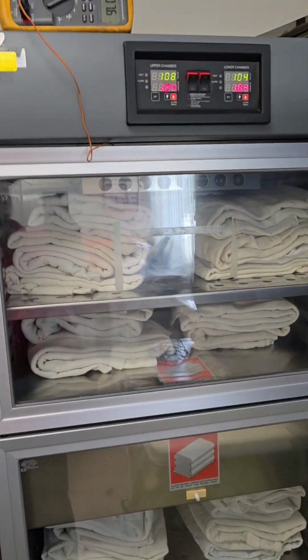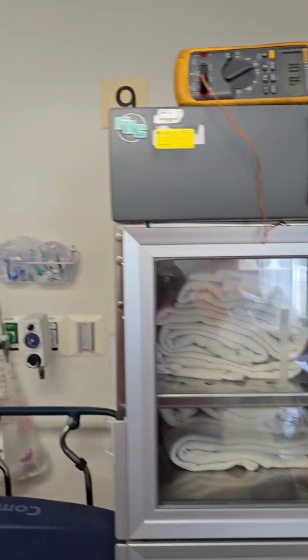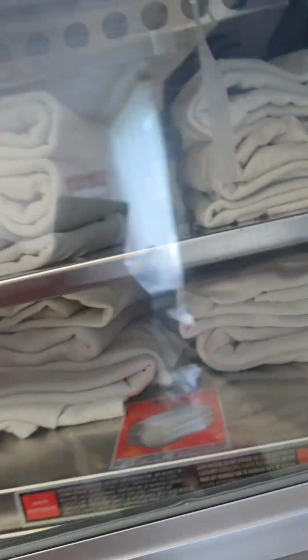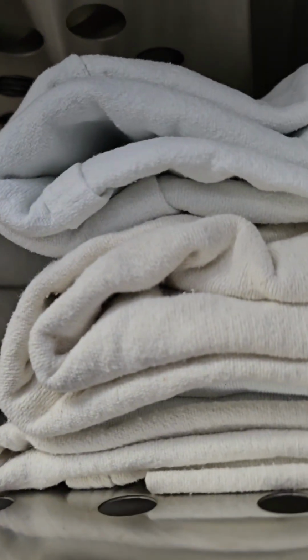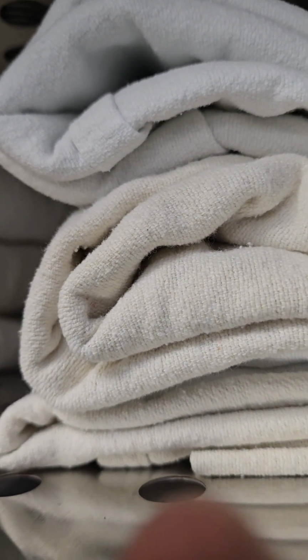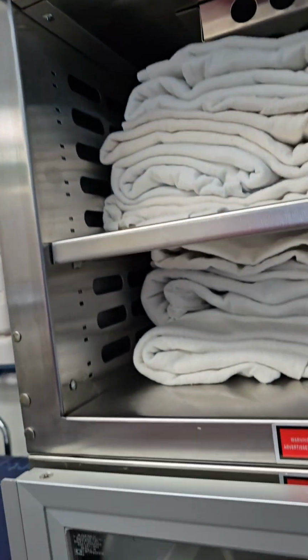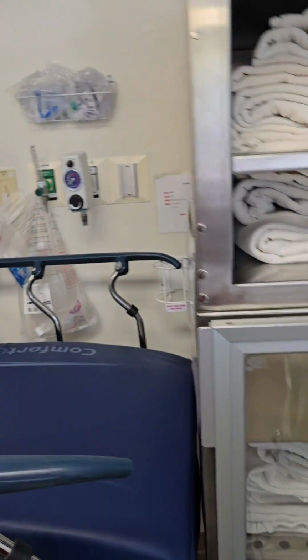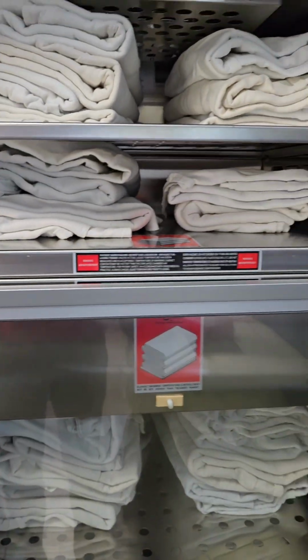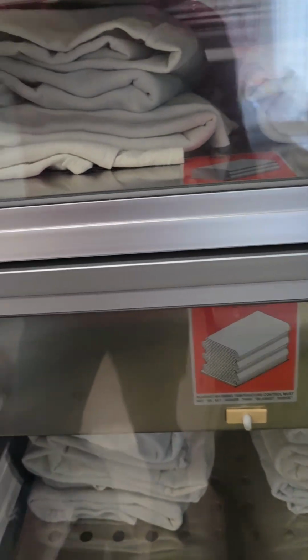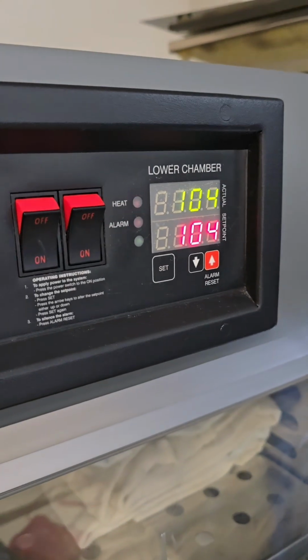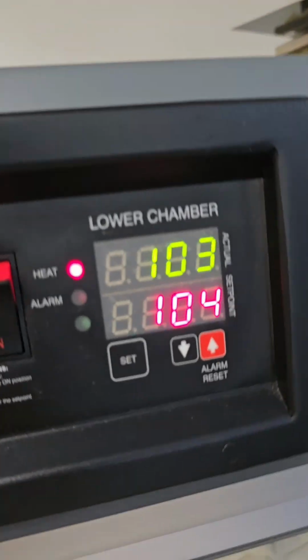How to calibrate the temperature on a MacMedical or FHC warming cabinet. This model specifically is a DWC24-G. So the first step is to get your probe, as I told you in other videos, close to the temperature probe of the cabinet you're looking to calibrate. Once that is done, close your door, give it about 10 minutes or so to reach temperature. It's just not fluctuating anymore.